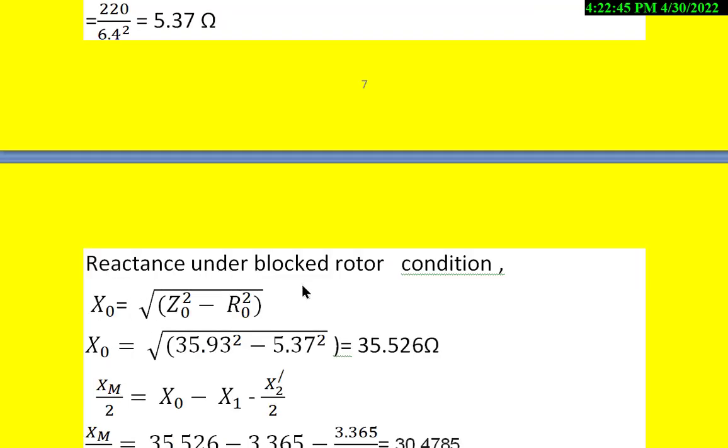Reactance under no-load condition: X0 = √(Z0² - R0²). Since Z0 and R0 are known, X0 = √(35.93² - 5.37²) = 35.526Ω.